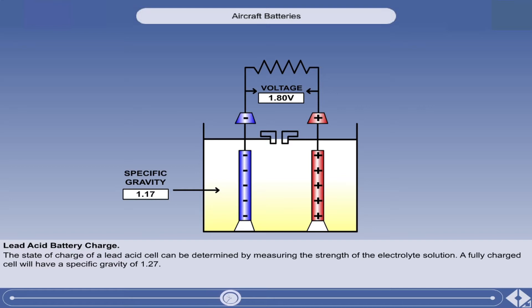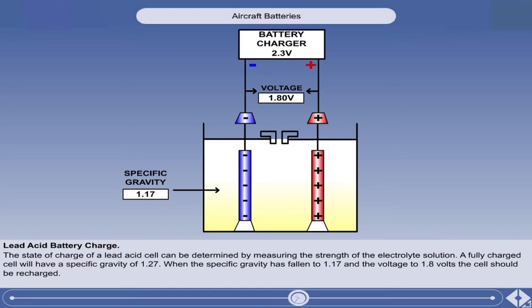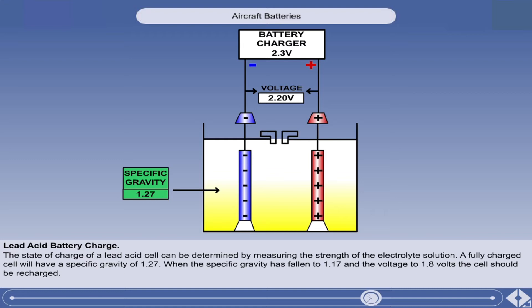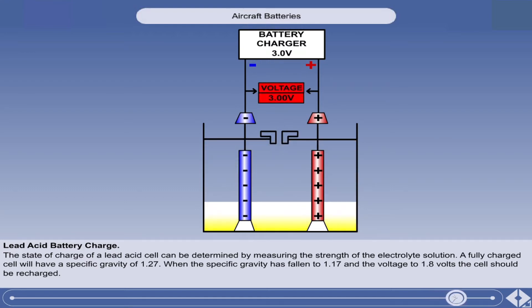The voltage also slowly reduces. When the specific gravity has fallen to 1.17 and the voltage to 1.8 volts, the cell should be recharged. To charge a cell, it is connected to a battery charger, which applies a slightly higher voltage to the cell and causes current to flow in the reverse direction through the cell. The current flow causes the chemical constitution of the electrolyte to change, producing an increase in its specific gravity back to 1.27. When charging a lead acid battery, it is important that the rate of charge is controlled. Charging too quickly can cause gassing and evaporation to occur, which may lead to a total loss of the acid, causing damage to the plates.